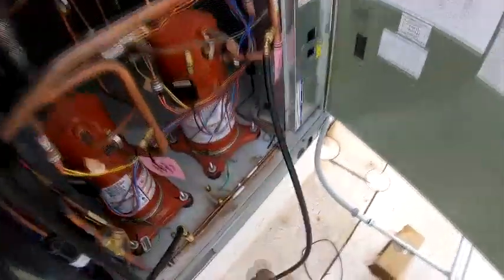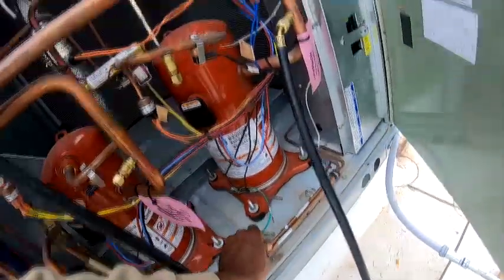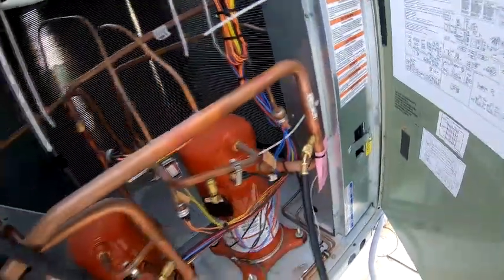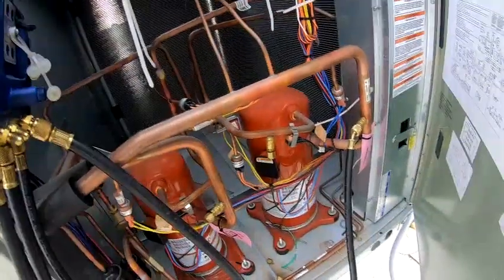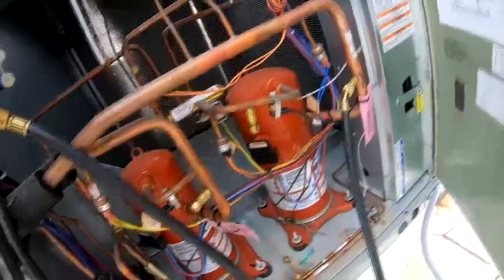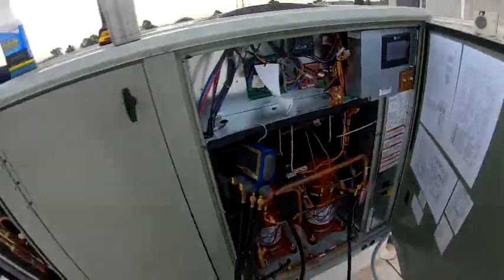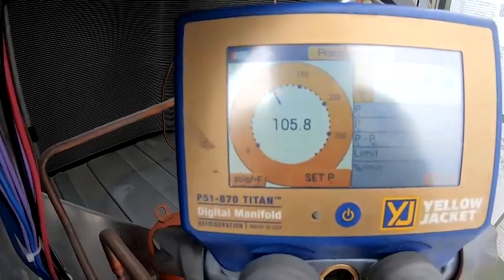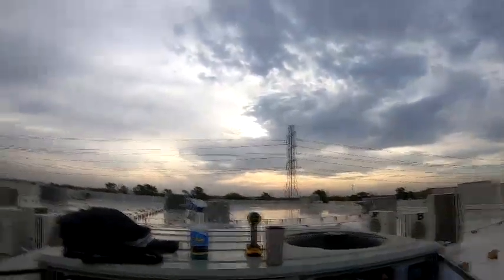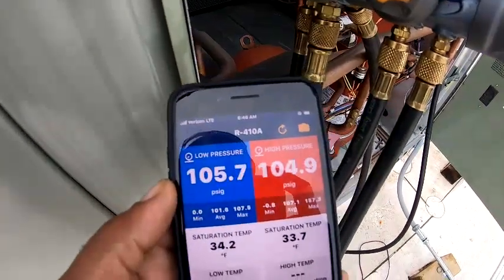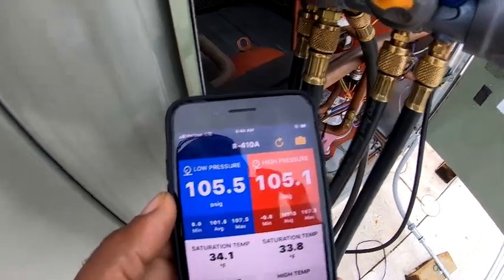But I got a suspicion, like I said, that this circuit 2 right here, them valves might still be leaking. But before I pull this Schrader, well, my service gauge is off, I'm gonna do a visual and spray some of these joints before I do that. Because as soon as I pull them off, I'm gonna lose a little bit of pressure. But it's staying around 105.8 and 106, so it might be all right, but gonna do a little investigation here. All right, so it looks like I am dropping. So I think we're gonna have a leak somewhere.